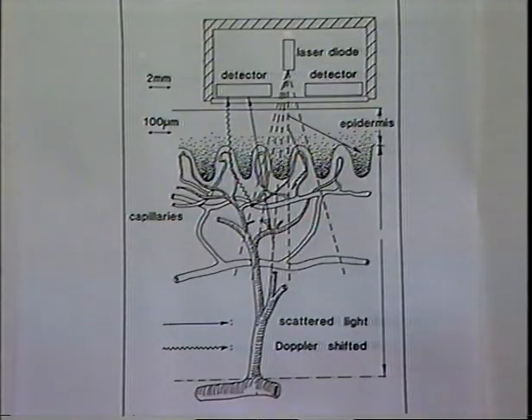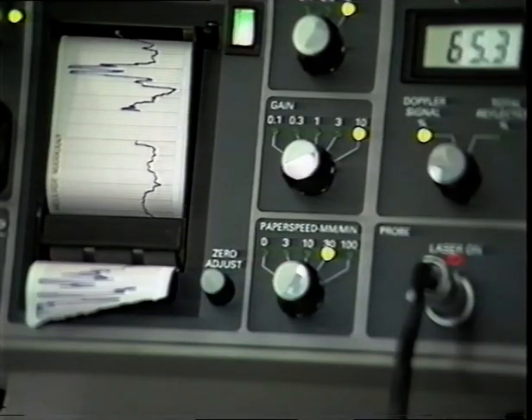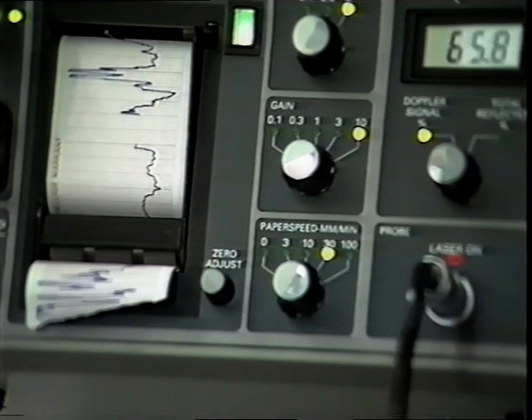In principle, the monochromatic light from the laser diode penetrates the skin where it is absorbed and scattered. The part of the light which is scattered by the moving red blood cells undergoes a slight frequency shift due to the Doppler effect. The Doppler signal is determined by the number of red cells and their velocities in the measuring volume, and the reflected laser light is registered by the laser Doppler Velocimeter probe, whereby output voltage is proportional to the velocity and number of moving red cells.